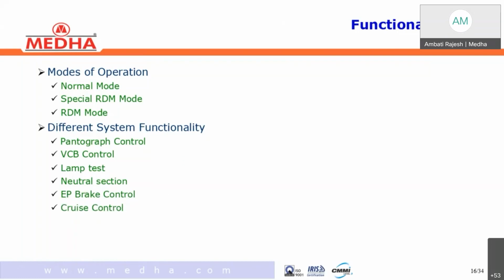Then cruise control. Sir, after passing the neutral section, do we have to press the ENS switch again? No, sir, only once. It is not required again. Only before the neutral section, at the 250 meter signboard, we need to press ENS once. After crossing the neutral section, whenever the OHE is re-established, the system automatically closes the VCB and exits the neutral section logic. Only for entry we need to press it once.